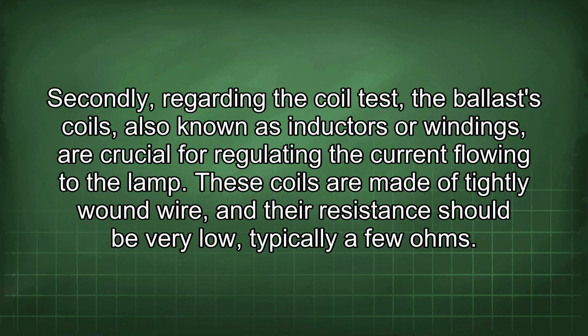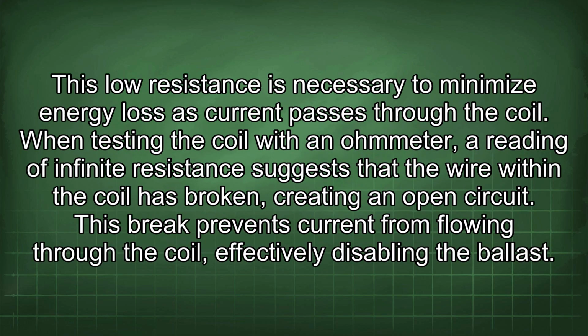Secondly, regarding the coil test, the ballast coils, also known as inductors or windings, are crucial for regulating the current flowing to the lamp. These coils are made of tightly wound wire, and their resistance should be very low, typically a few ohms. This low resistance is necessary to minimize energy loss as current passes through the coil. When testing the coil with an ohmmeter, a reading of infinite resistance suggests that the wire within the coil has broken, creating an open circuit. This break prevents current from flowing through the coil, effectively disabling the ballast.